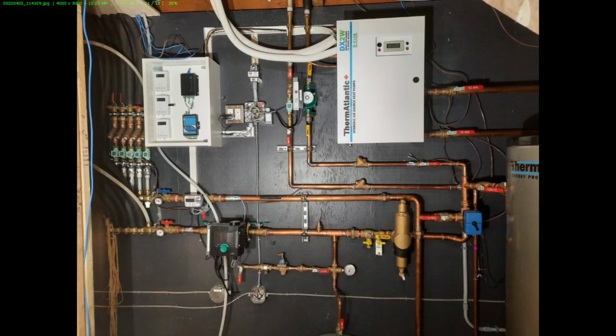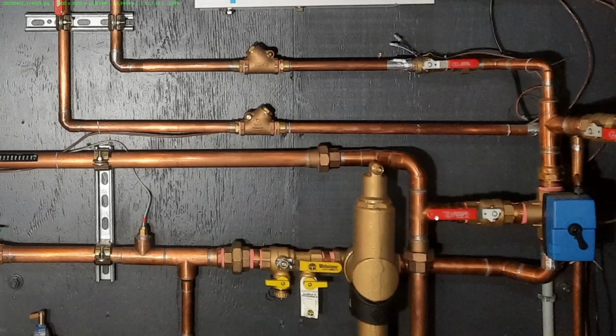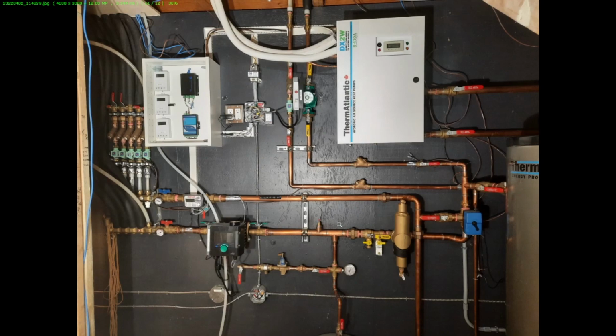Got our mixing valve. So what happens is the water comes back from the panels not as hot as it went out. So it's, say, warm water instead of hot water. It will get mixed with the water coming off the buffer tank if the temperature needed by the panels, which is going out this way, is less than what's in the buffer tank. So it allows for the buffer tank to be cycled with a reasonable on-off deadband, so we're not overtaxing the heat pump. And then we can basically ramp up or down this mixing valve to allow for a common output temperature that matches what we figure out we need based on the heating load of the house and the outdoor air temperature.